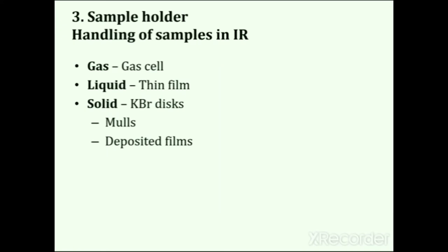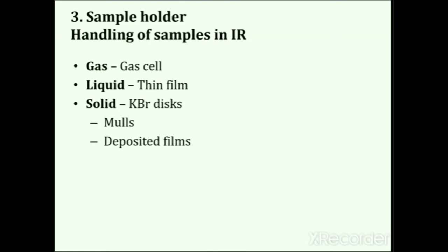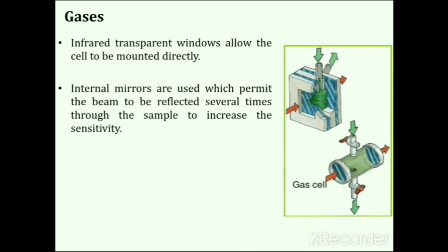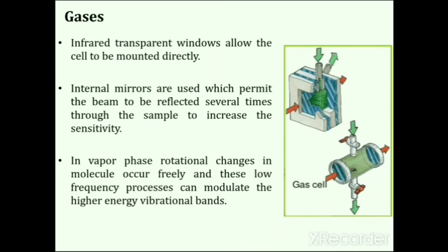Next part is the sample holder, used for holding the sample. Sampling techniques in IR depend on whether the sample is a gas, liquid or solid. For gas samples, a gas cell is used — the gas sample is inserted in the cell, mounted between infrared transparent windows. Internal mirrors permit the beam to be reflected several times through the sample to increase sensitivity. More reflections increase the chances of interaction of IR radiation with the gas sample. In vapor phase, rotational changes in the molecule occur freely, and this low-frequency process can modulate the higher energy vibrational bands.